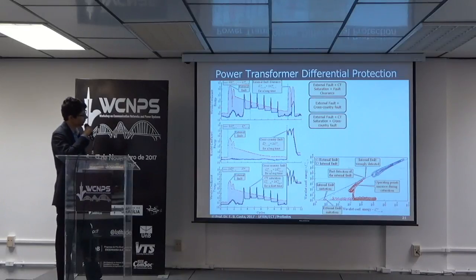The Wavelet Transform can also detect the current transformer saturation. So during the current transformer saturation, the protection can be blocked. However, if an internal fault takes place, the wavelet-based protection can detect it and can trip this protection. The transformer can be protected.